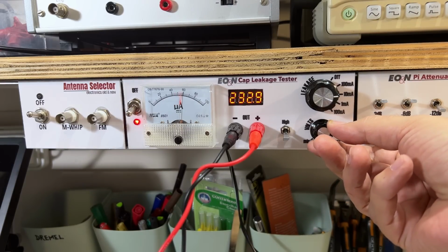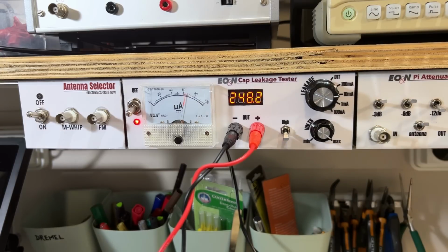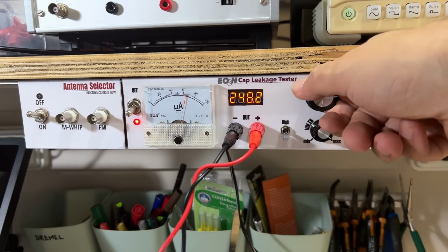Watch this. Well, there we go. 250 volts, and it's leaking. On the 10 milliamp range, it's leaking 6.5 milliamps. This capacitor is so dead, it's not a joke.